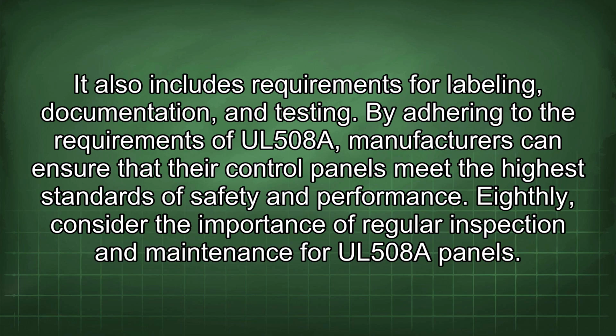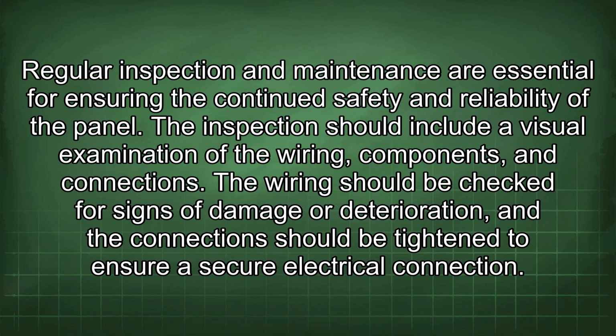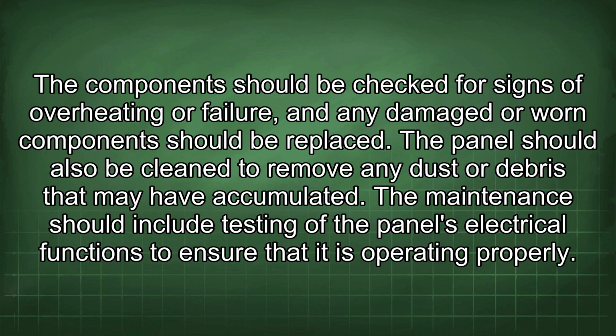and performance. Eighthly, consider the importance of regular inspection and maintenance for UL508A panels. Regular inspection and maintenance are essential for ensuring the continued safety and reliability of the panel. The inspection should include a visual examination of the wiring, components, and connections. The wiring should be checked for signs of damage or deterioration, and the connection should be tightened to ensure secure electrical connection. The component should be checked for signs of overheating or failure, and any damaged or worn component should be replaced. The panel should also be cleaned to remove any dust or debris that may have accumulated.